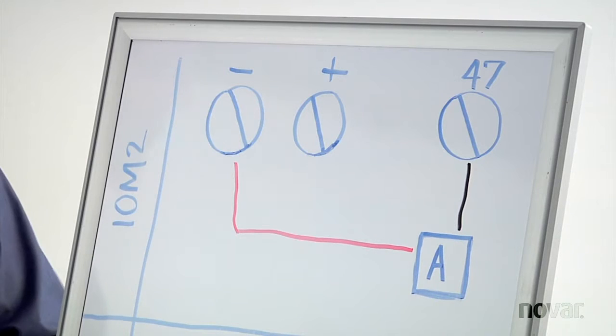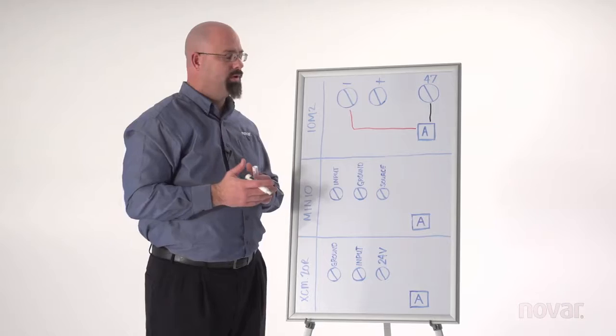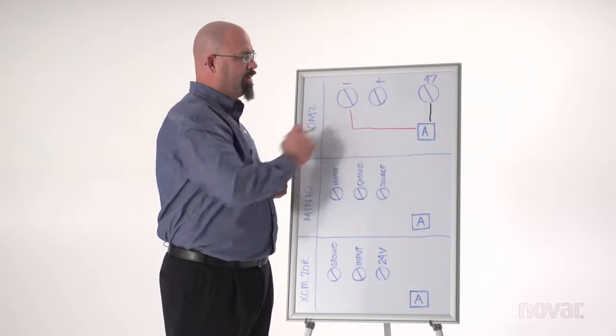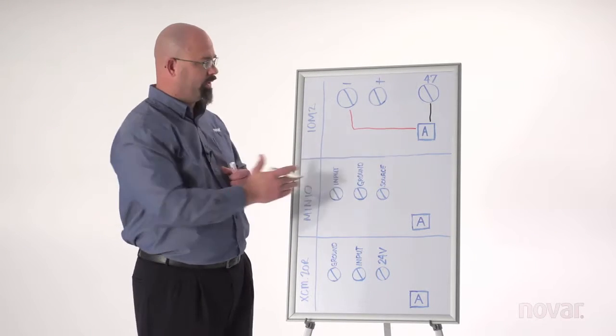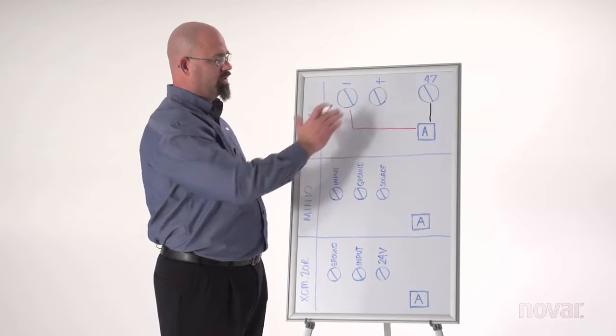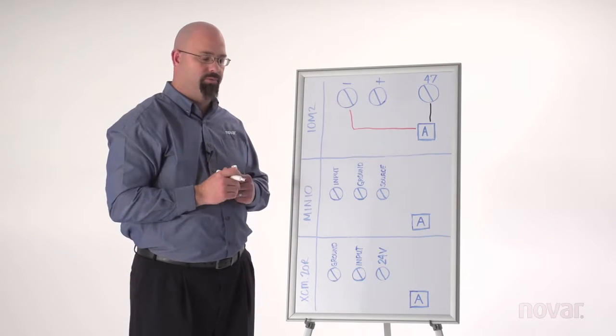Now right next to it, terminal 48 is also the earth ground. And 47 is the common terminal for all the sensors that are remotely powered in this case. I like to keep them separate. 47 for all the sensors, 48 for the ground of the IOM-2 itself.